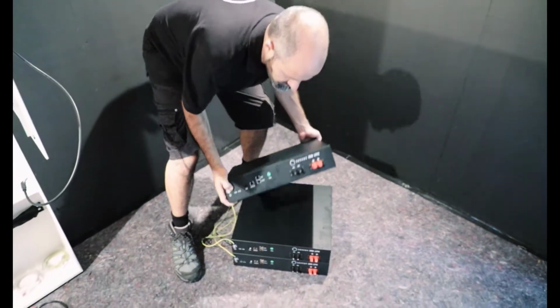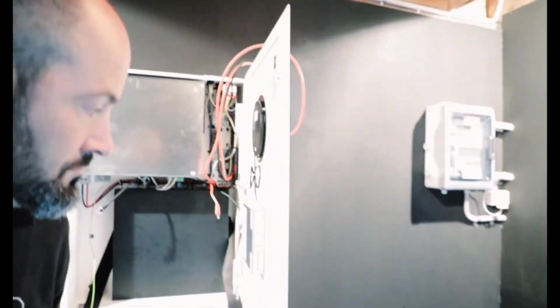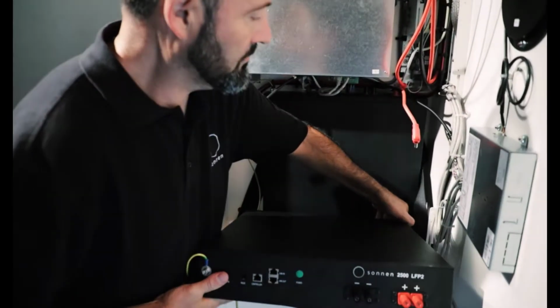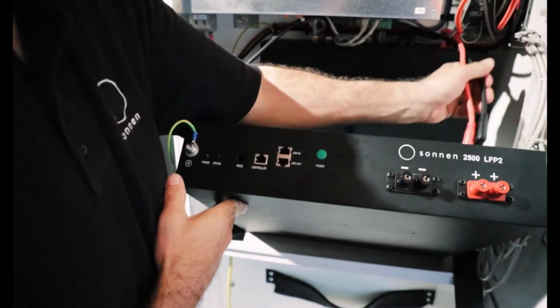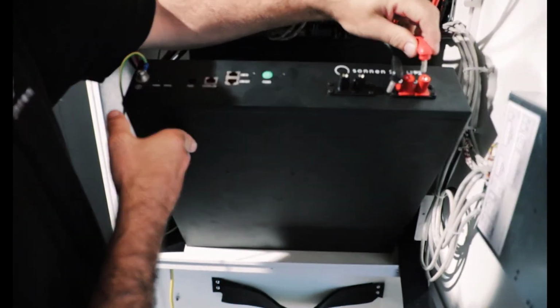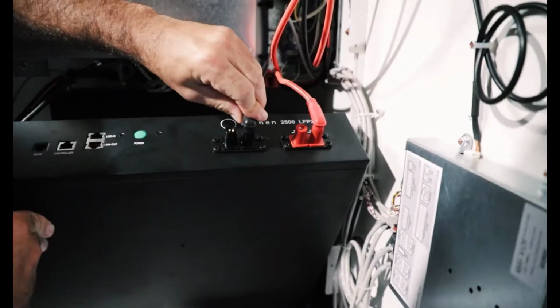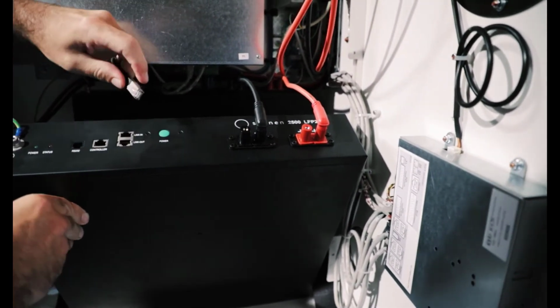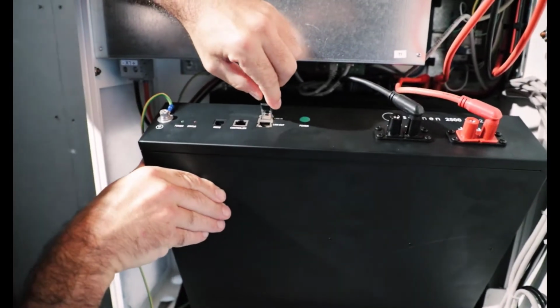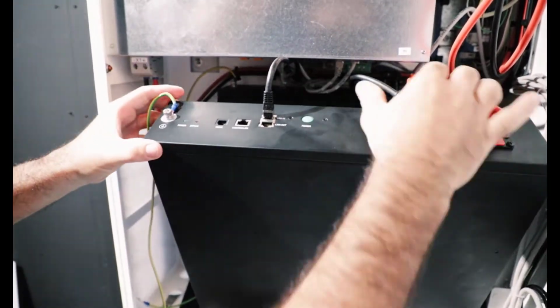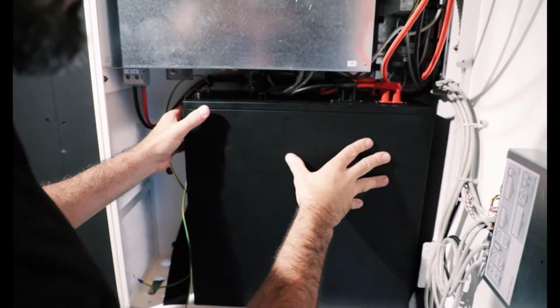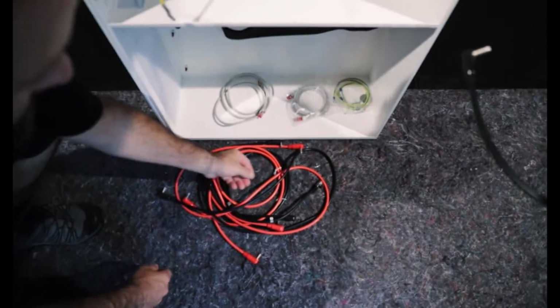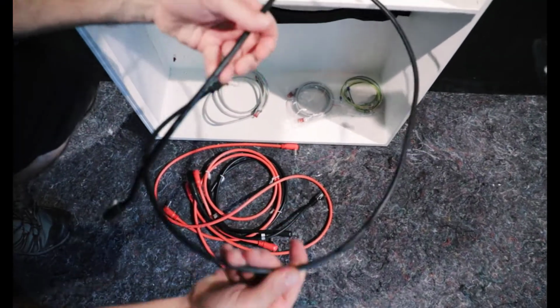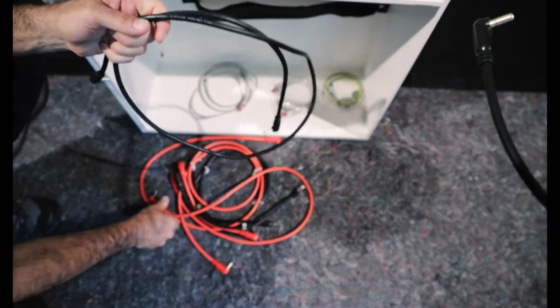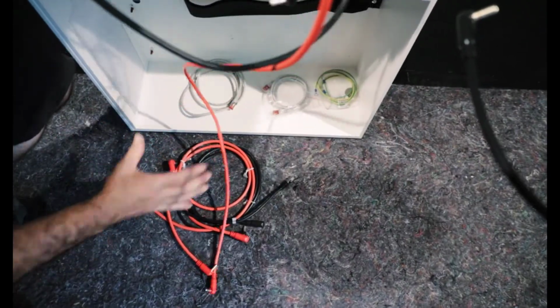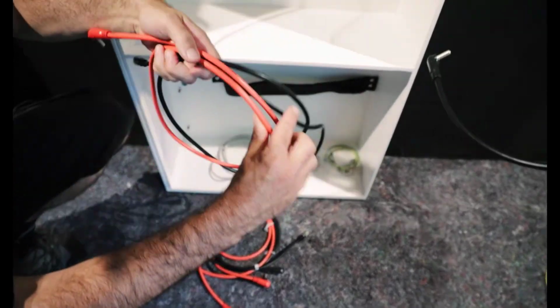Taking battery number 2 and simply installing that in front of number 1. Connecting in the positive and negative terminals. So again, as the batteries are turned off, in the C-bus there, we plug that into in, and then it goes from out from battery number 1 to in on battery number 2. Now as the batteries are, like I said, turned off, there is no arc hazard with these battery modules at all. Very important feature when considering AS5139.